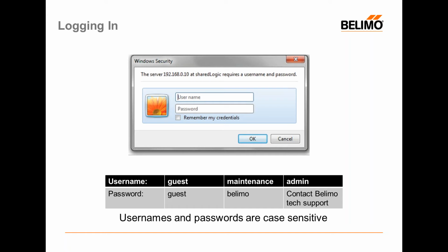Finally, we have an administrative level setting, which here you see on the screen. We do not openly provide the username or password for that. You have to contact either Belimo Tech Support or your local district sales manager for the admin level password. With the admin level password, you can go in and actually make changes to the settings of the valve, essentially reconfigure it so the valve will function differently for specific flow rates, delta T manager routines, things of that nature. So again, if you are a higher level tech or user and you need to get in at that admin level, either contact our tech support folks or your local sales manager, and he or she can get you those credentials.